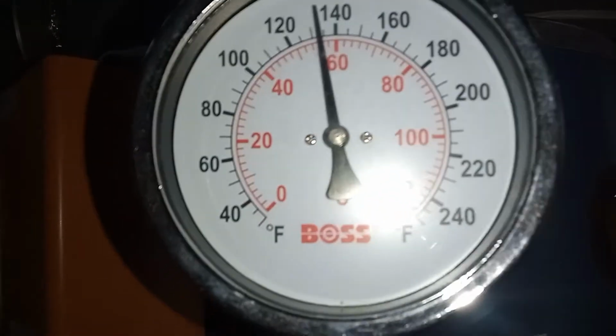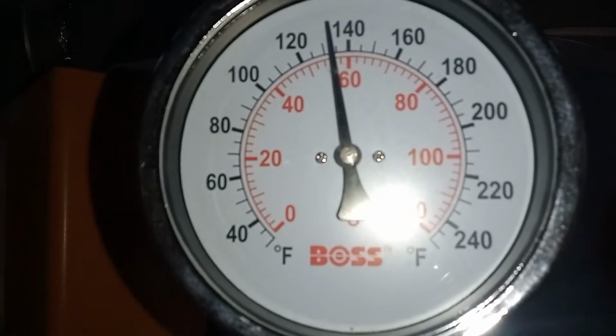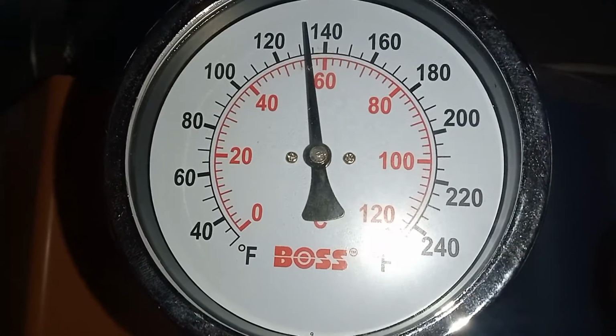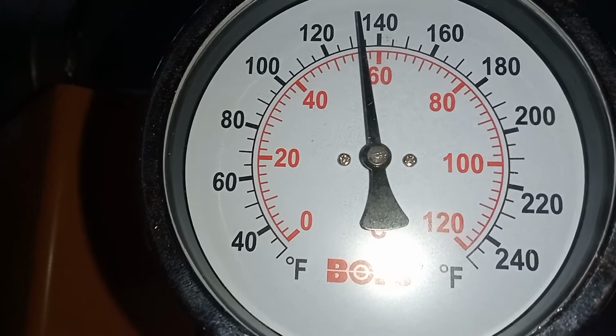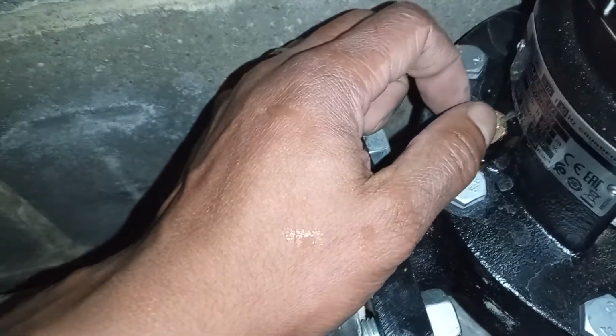So continuing to monitor our temperatures here, because there's been a change in the system. Don't want anything happening, don't want them overheating, nor do we want them dropping too low because of Legionella. And still venting my pump a bit.